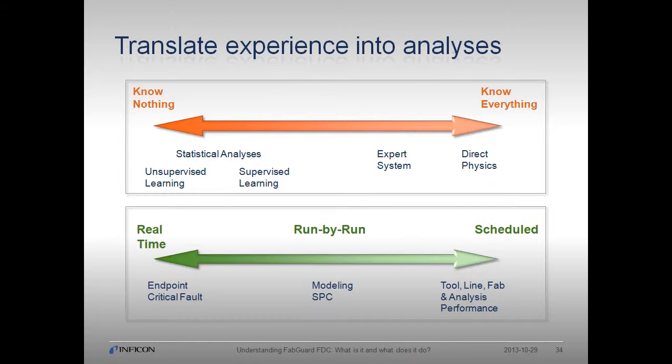From a time perspective, FabGuard can operate in real-time — analyses applied to each new data point as it's collected. Process endpoint or critical faults are generally performed using real-time analyses. FabGuard can also operate on a run-by-run or wafer-by-wafer basis; typical SPC reports and certain models are applied to summarized run-by-run data. Meta-analyses can also be scheduled to run periodically, such as an SPC health check, CP/CPKs, a Pareto of tool alarms in an area, or a list of current RF hours for each tool in a group for PM planning.